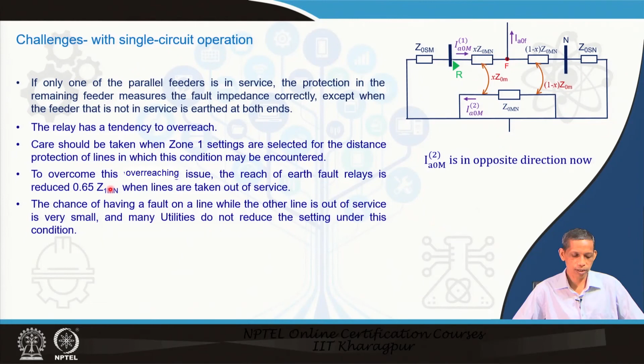However, such a fault during single circuit operation, with the other line grounded, is very rare. So, many utilities do not go for this lower setting of zone 1; they continue with the highest normal setting of 0.8 to 0.9 of the Z1Mn.